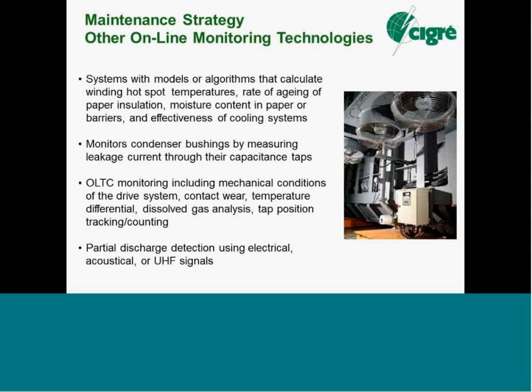We'll repeat some of those points I just made. There are some pretty sophisticated monitoring technologies, and we bring these to bear. We invoke these sorts of more specialised, more esoteric monitoring systems when maybe one of a group of transformers fails in a particular way. We realise that there's a bit of a common mode failure, and we need to focus on that particular mode of failure. It may need specialised transducers to do this online. And partial discharge detection, whether that's electrical, acoustical, or UHF signals, is probably one of the most complicated but very powerful techniques for trying to discern electrical failure, or rather the pre-breakdown phenomena before electrical failure.